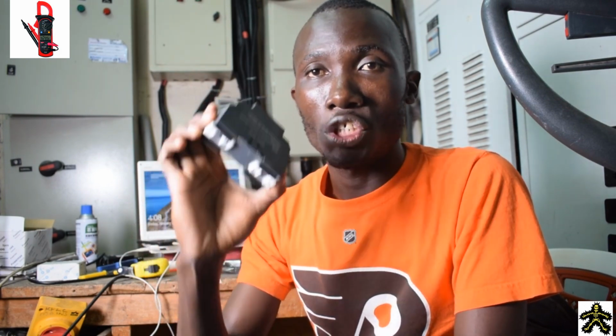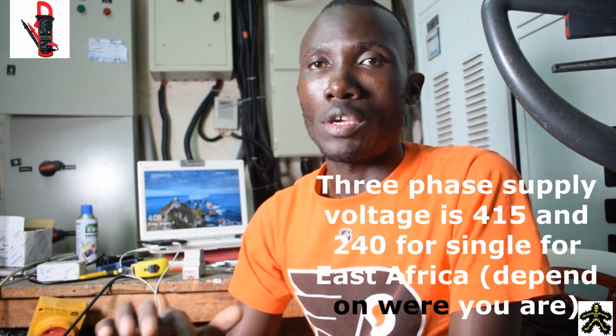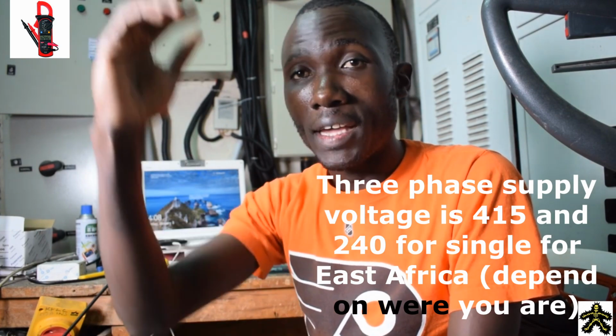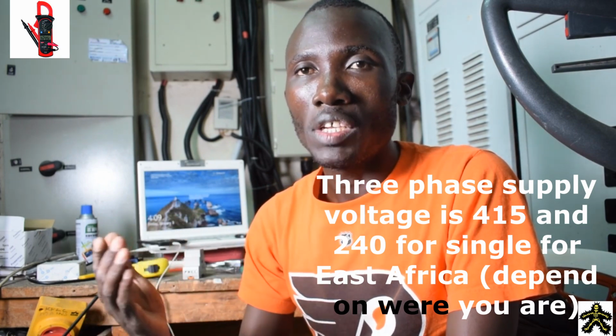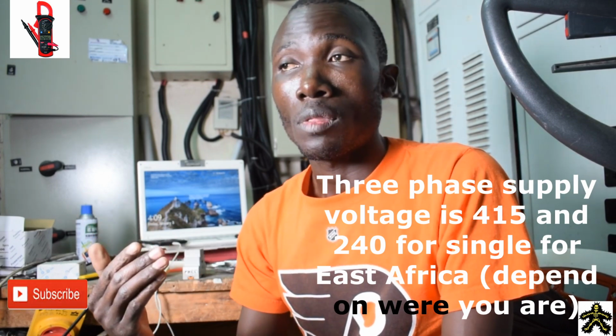The other thing is that it protects your drive from under voltage and high voltage. For example, in our country here in Kenya, the supply voltage is always 415. So when you're setting your parameters, you should set the threshold on high and low. For example, if it's 415 and it comes to maybe 500, that's high. 420, that's high. So you set between there, maybe at least 415, then at 417 it breaks. Then under voltage also, because you know very well that under voltage can ruin machines. It's really, really bad for them.